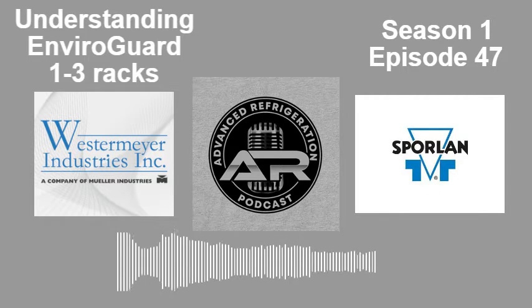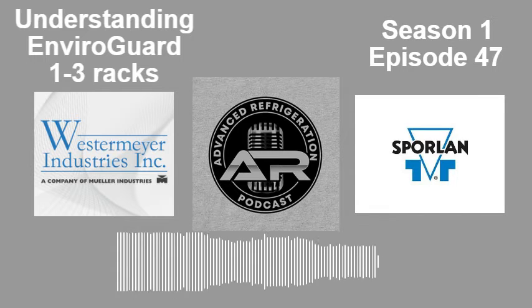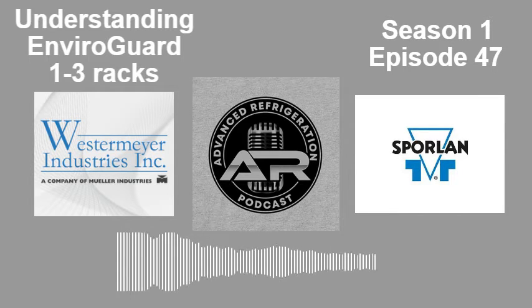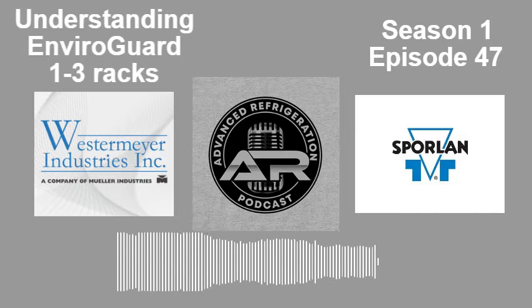The whole premise and theory behind Enviro-Guard is, I believe some dude in Michigan made this. I'm not for sure, but he had the original design. Enviro-Guard is a floating head pressure critically charged rack. When floating head pressure first started coming around was when the Enviro-Guard was coming out. The whole theory behind this is we no longer have a receiver.